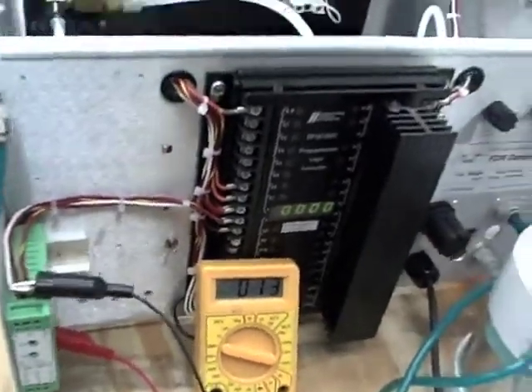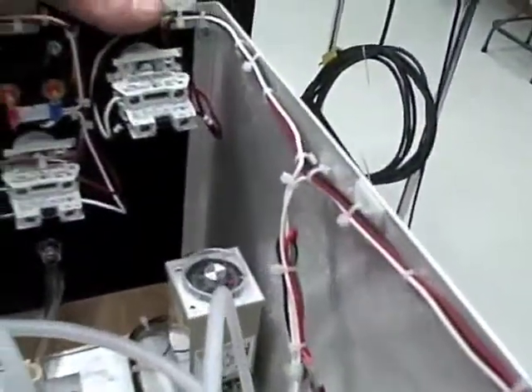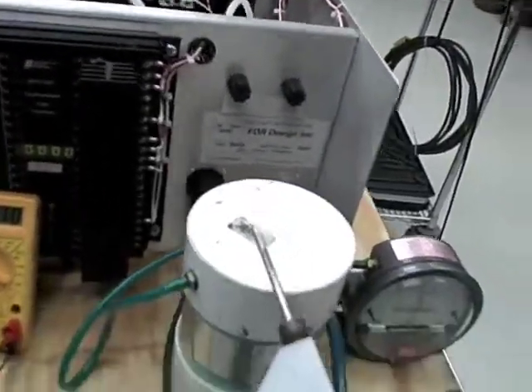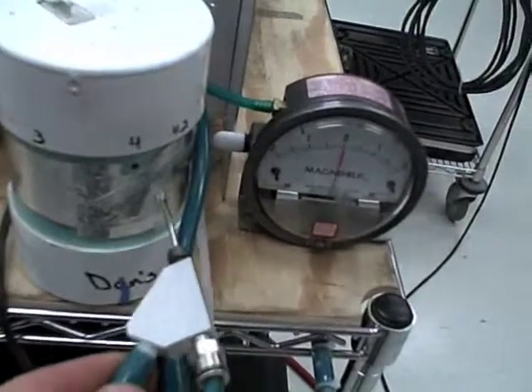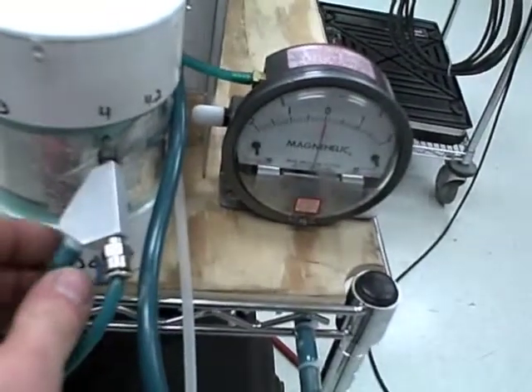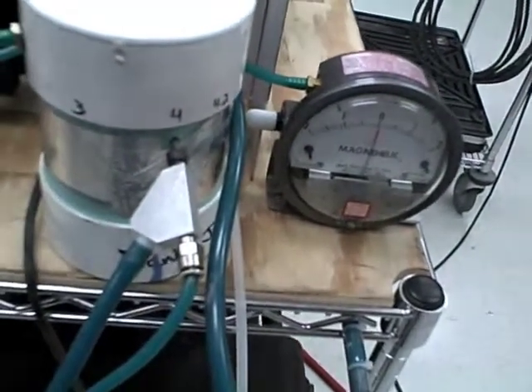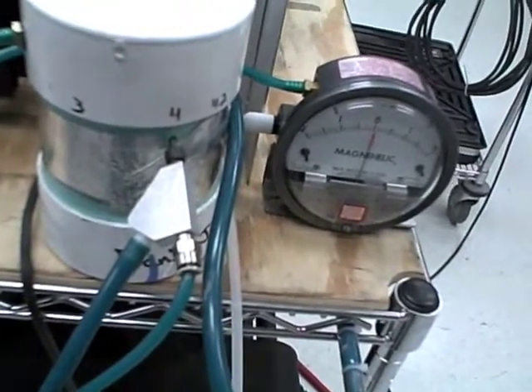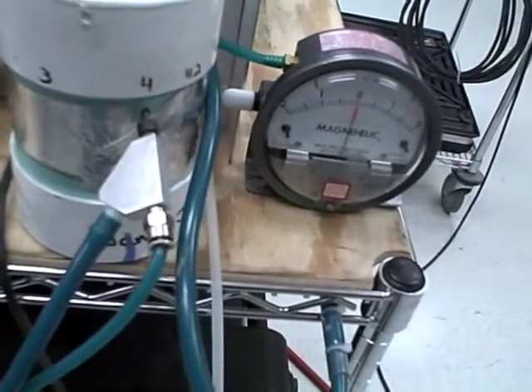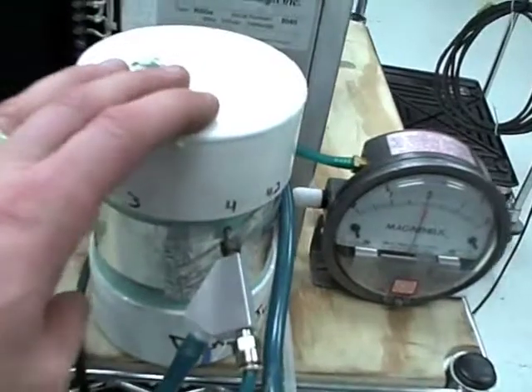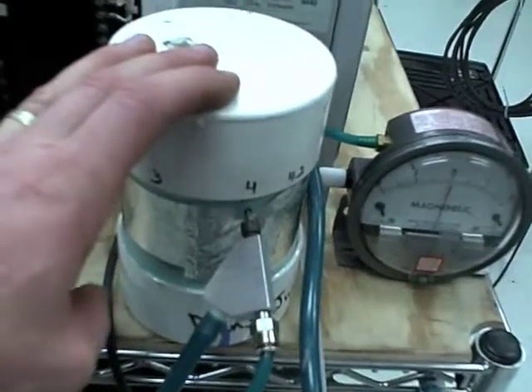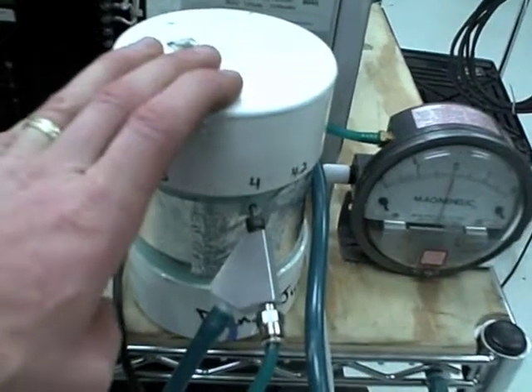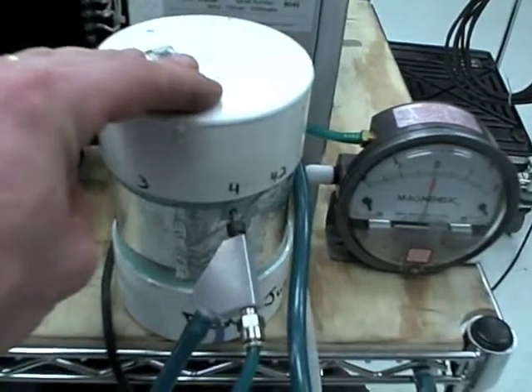Alright, then after we get the 13 millivolts, we'll just hit the stop button again. Now we're going to take the filling lance and put it in the test jug, and I'm just using a 4mm hole here, but you'll want to use a hole that's the same size as the hole in your spacer bar, because what we're doing with this test jug is actually replicating the actual unit that we're going to be filling, and you want to do that as closely as you can.